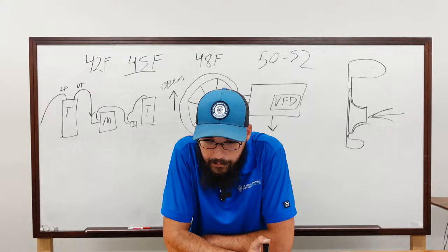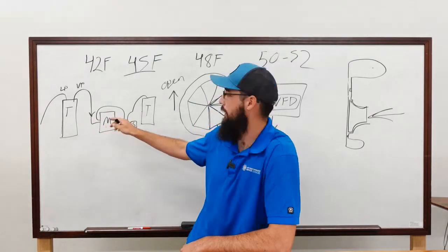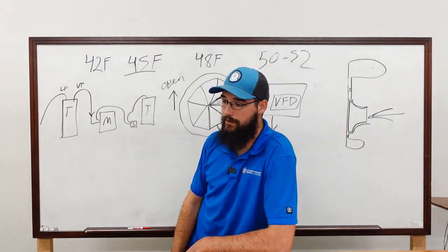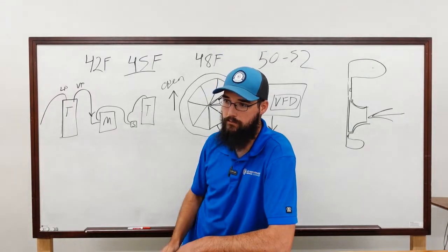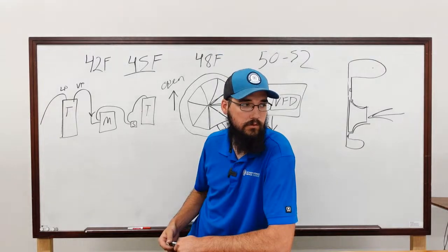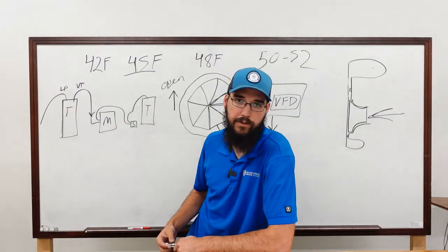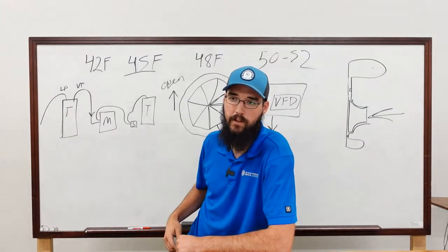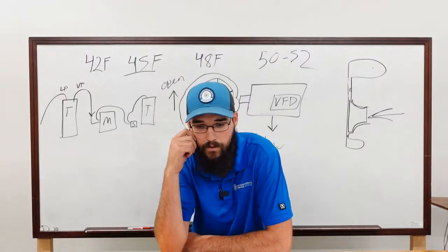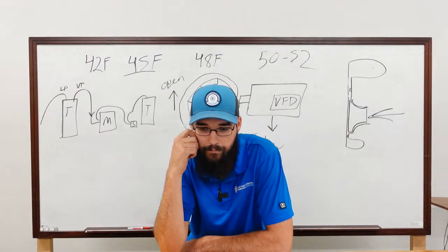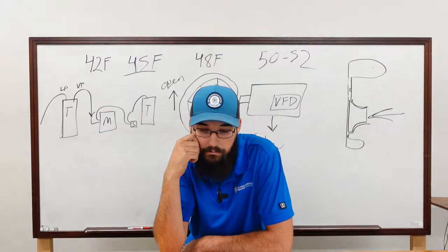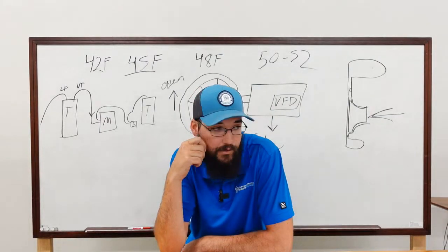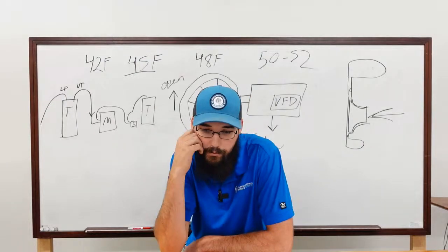What's the recovery time with that method? Doing this, I can do 1,000 pounds in somewhere between 6 to 8 hours on a low pressure recovery, give or take, without any major hiccups. So push-pull, you say you can get 80% in 2 hours, 1,200 pounds? Yeah, you're still having to deal with vapor. That's the thing, you're dealing with vapor recovery still. You still have a lot of vapor to deal with.